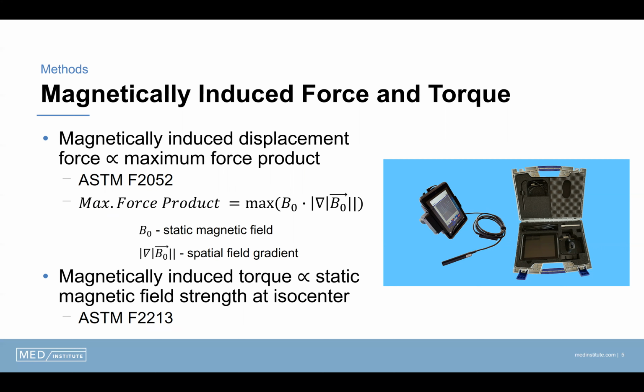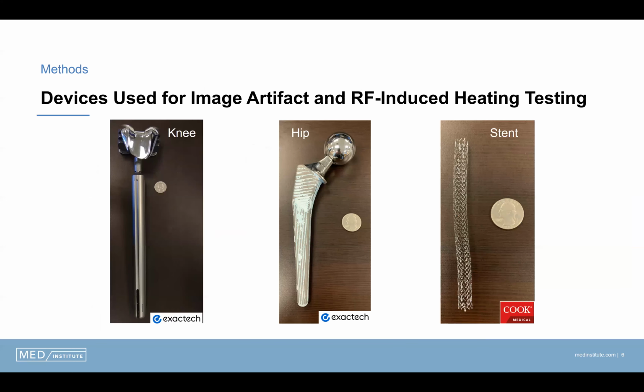The Tesla meter reading at isocenter was used as the evaluation of magnetically induced torque for devices in each MRI system, since devices are tested for torque at isocenter according to ASTM 2213. The magnetic field strength at isocenter is directly proportional to the magnetically induced torque of a given medical device in an MRI system. 3 commercially available medical devices were used to evaluate image artifact and RF-induced heating of the various field strength MRI systems. These included a knee and hip prosthesis from Exactech and a cardiovascular stent from Cook Medical.